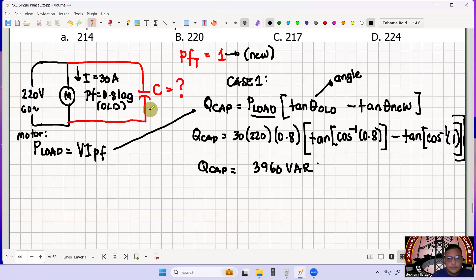Minus tangent theta new, we just get the inverse cosine of 1. So what's your Q cap now equal to? 30 times 220 times 0.8 times the quantity tangent of arc cosine of 0.8 minus tangent of arc cosine of 1. This is now equal to 3,960, and this is in VAR.